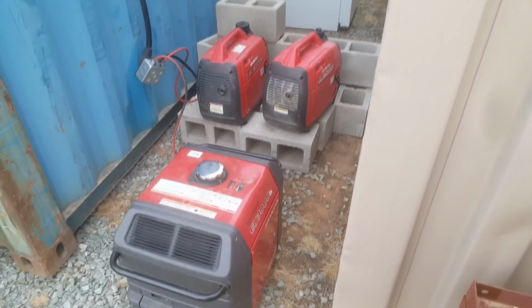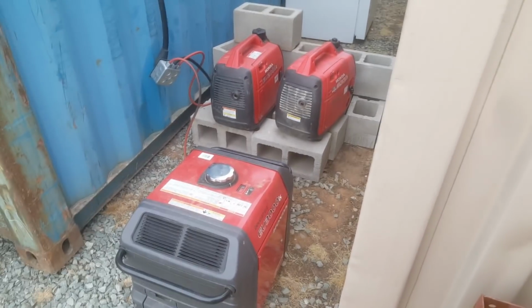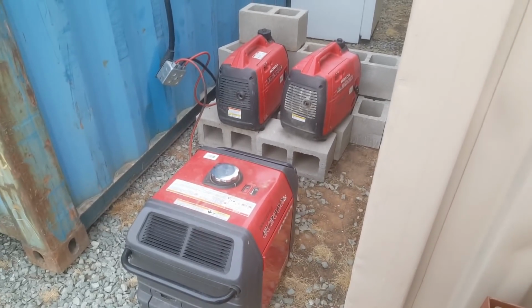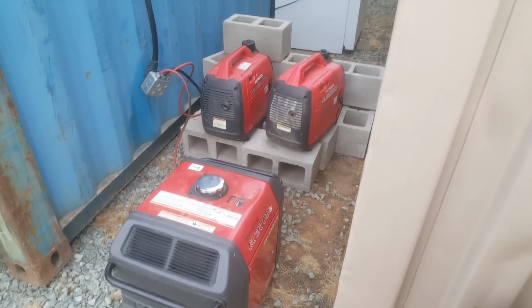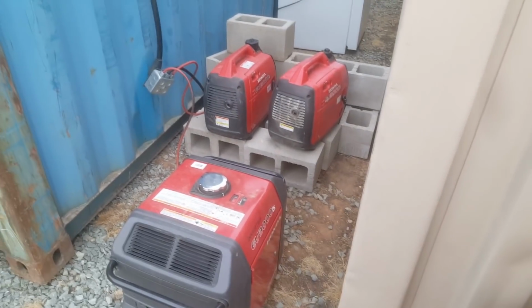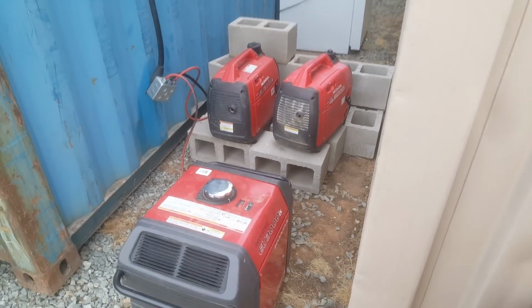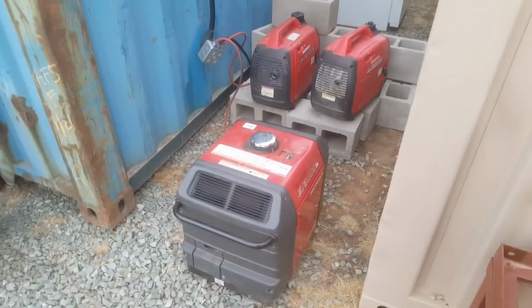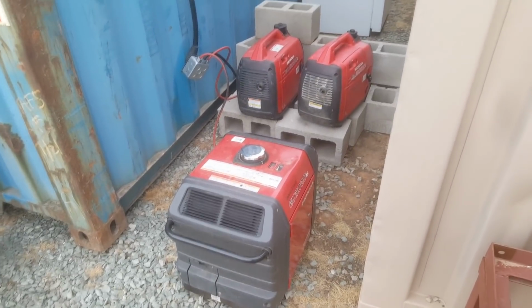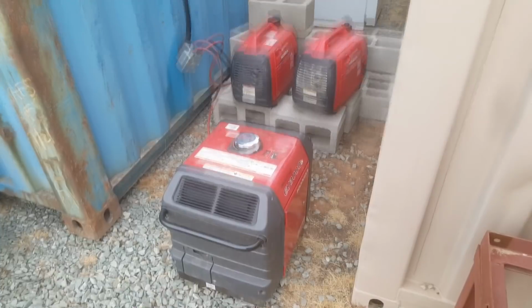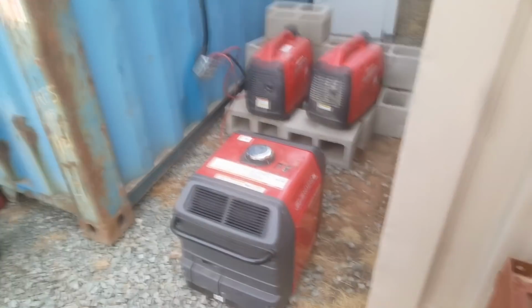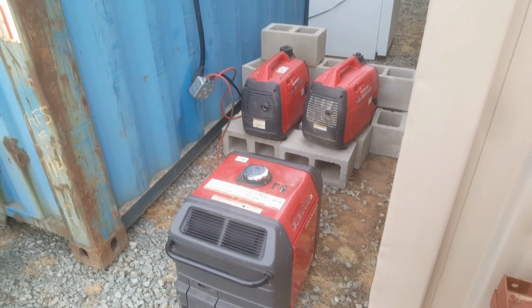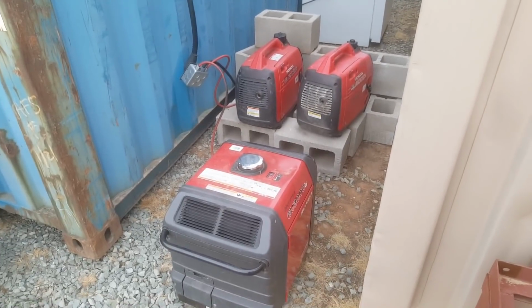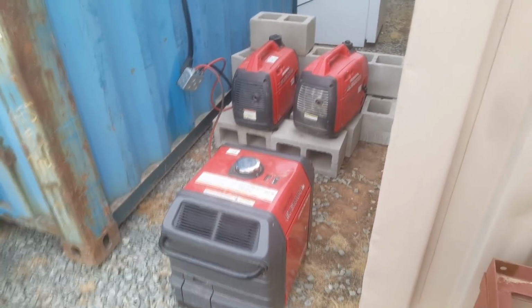But one of the downsides is the battery charger transfers over to the generators, which means all loads are then on the generators. So if these are running and you start up the dryer, for example, it'll easily overload these generators. I would like to replace this with approximately an 18 kilowatt diesel generator. That way I can run up to 12,000 watts, which is the load of the inverter at full capacity, plus another 6,000 watts for the battery charge of the inverter.